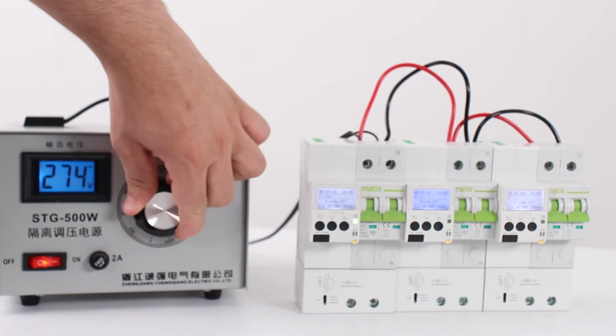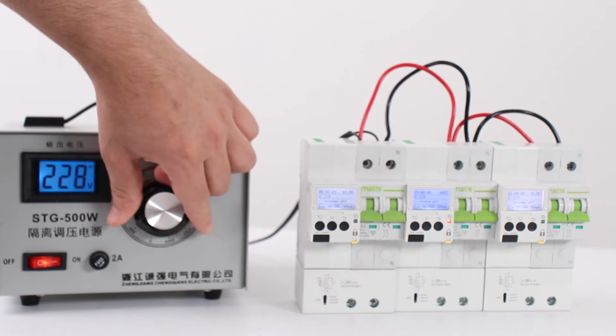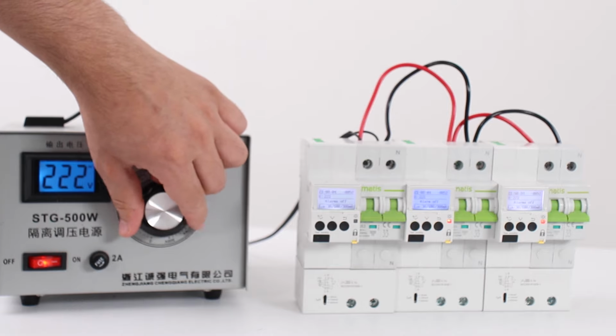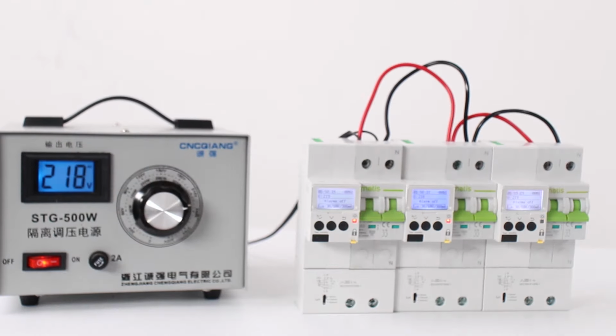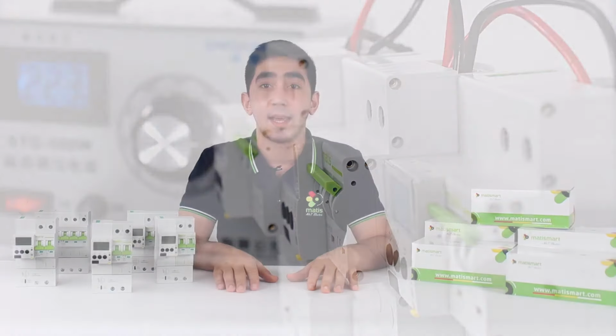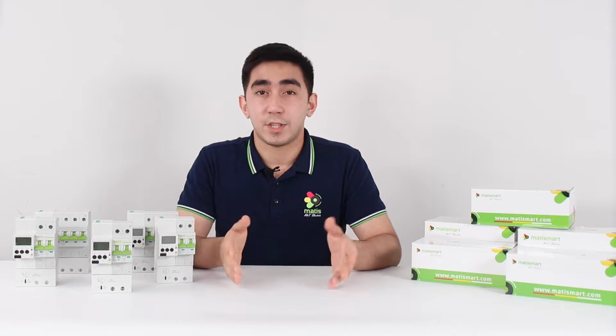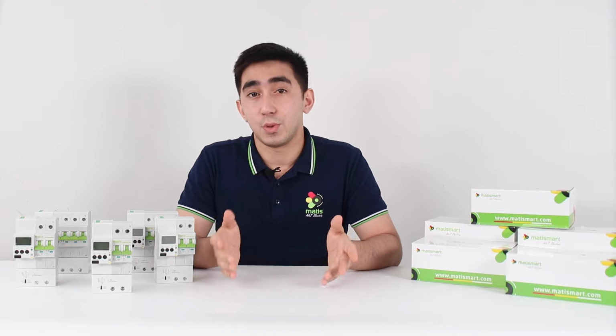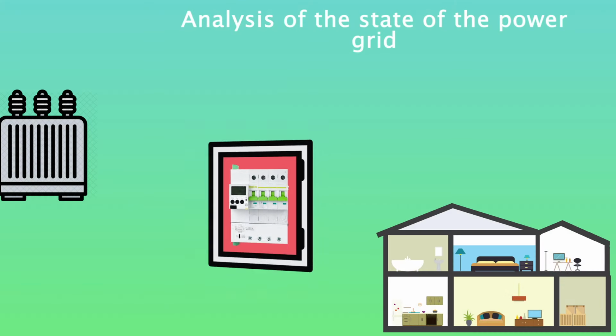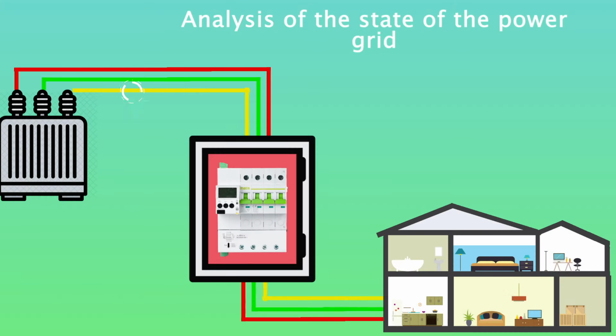The device is under the influence of high voltage and is disconnected. Let's restore the voltage to the operating range and see what happens. As you can see, the device turned on automatically within 1 minute. If you are wondering why for so long, then there is a good reason for this. The device checks the state of the power supply for 1 minute. And if the voltage remains in the operating range during this period of time and there are no other problems, the device will automatically turn on.